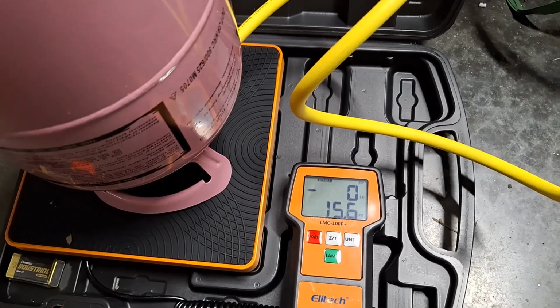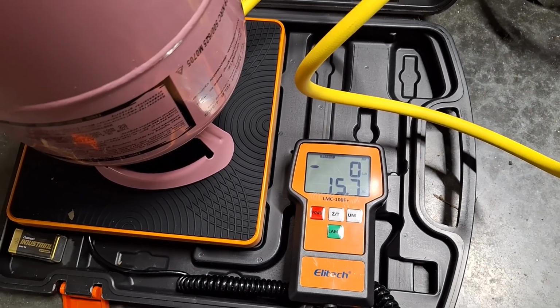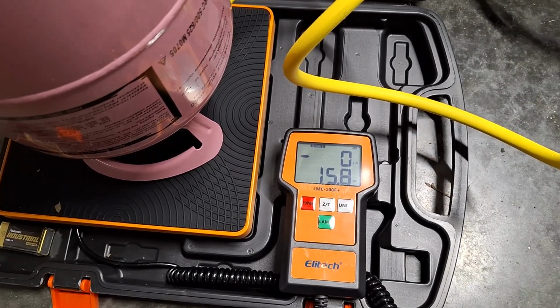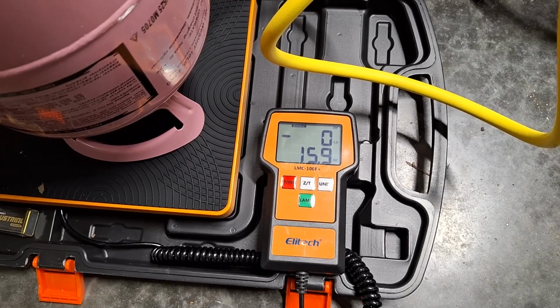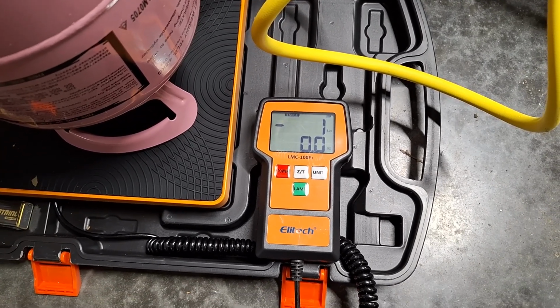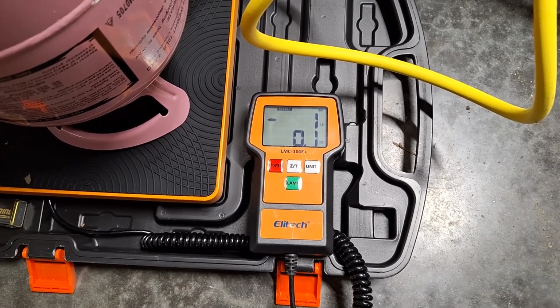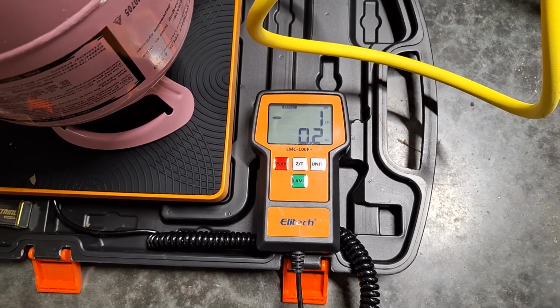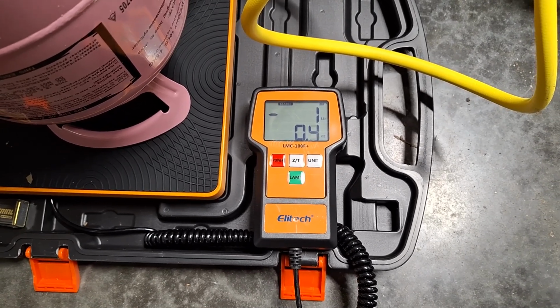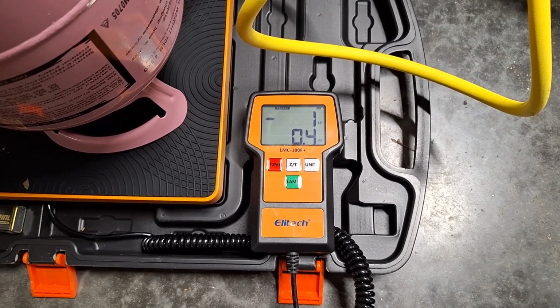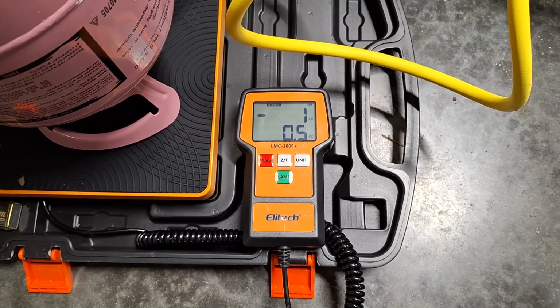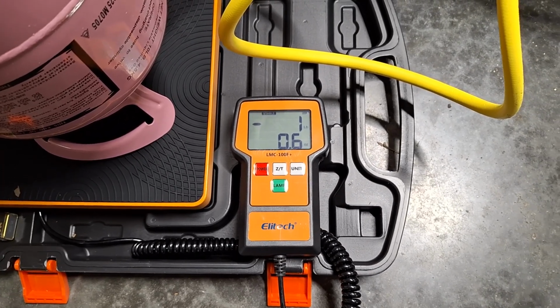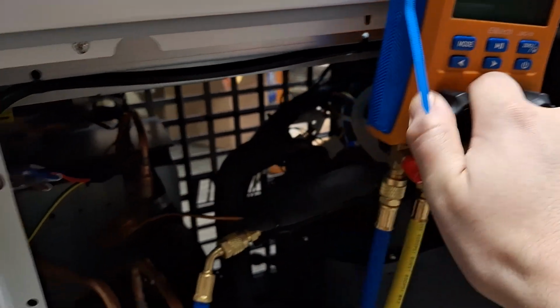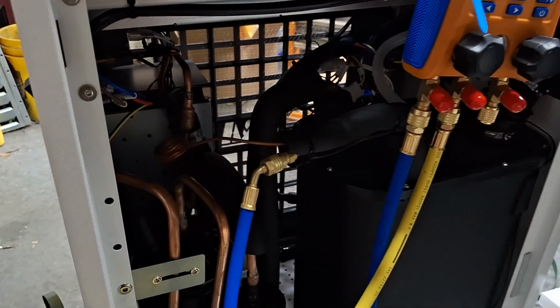Back to the part where I was talking about the liquid and gas. When you have the tank upside down, it's really putting out more liquid because all the liquid goes down to the bottom where the valve is, and it's coming out as liquid for the most part. You don't really want that liquid going directly into the chiller. You want to limit the flow with the valve on the manifold gauge so it has a chance to turn into gas before it enters the chiller.